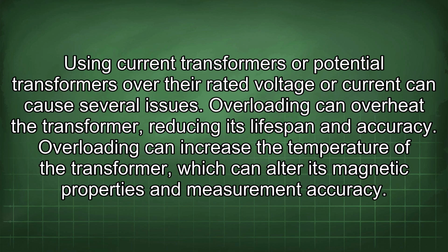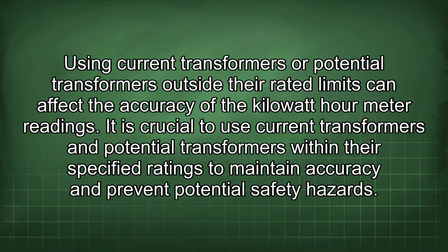Using current transformers or potential transformers over their rated voltage or current can cause several issues. Overloading can overheat the transformer, reducing its lifespan and accuracy, and can increase its temperature, which can alter its magnetic properties and measurement accuracy. Using them outside their rated limits can also affect the accuracy of the kWh meter readings.